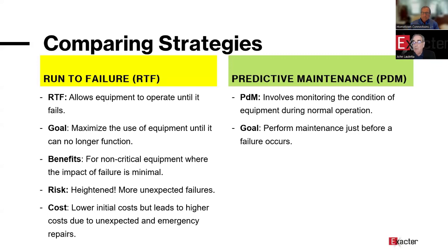So what we want to do in predictive maintenance is, rather than wait for the failure, we want to use the condition measurements of the equipment to let us predict it's probably going to fail, and soon. It's an incipient condition. That if it fails, we're going to lose this circuit, we're going to affect this hospital, we're going to have so many customers without power, and that's going to rack up our CMI and hurt our indices of SAIDI and SAIFI, and we don't want that to happen. So when we can predict a failure, we can do something about it early.